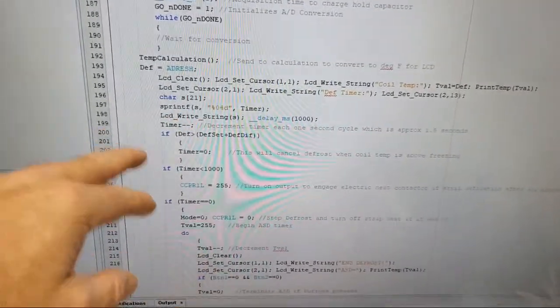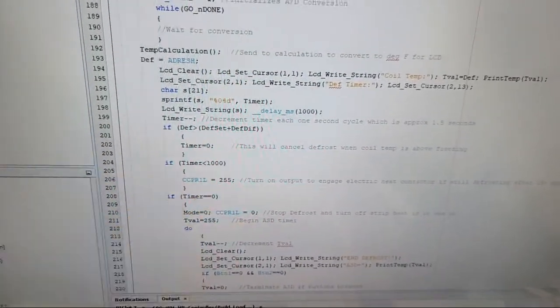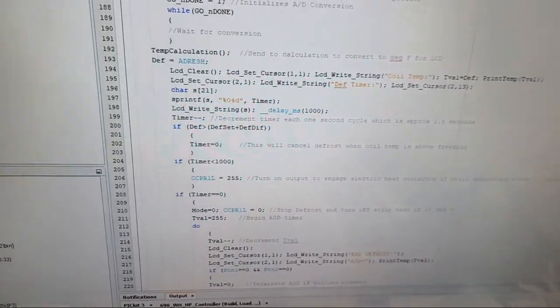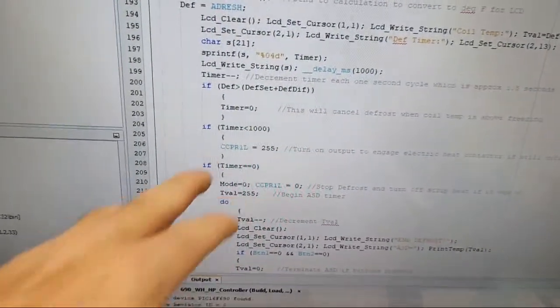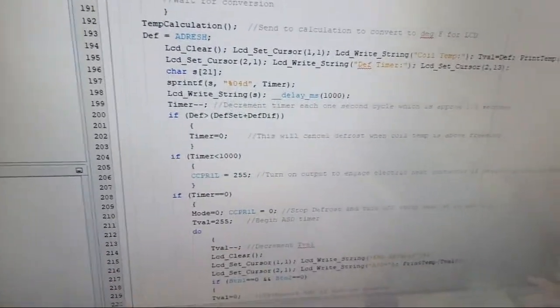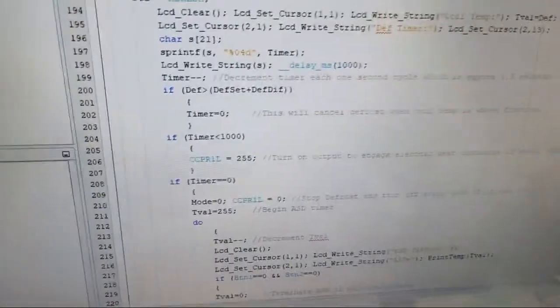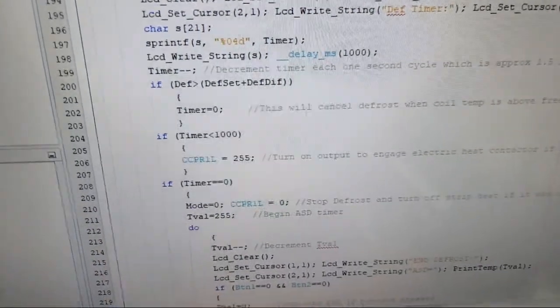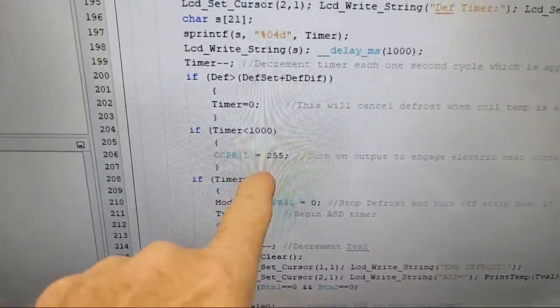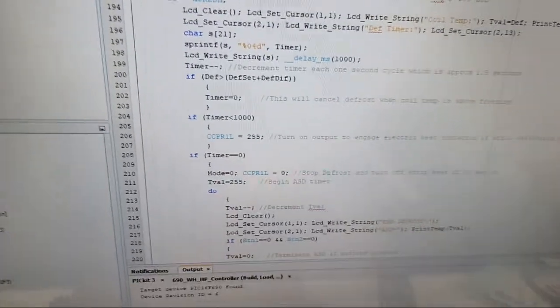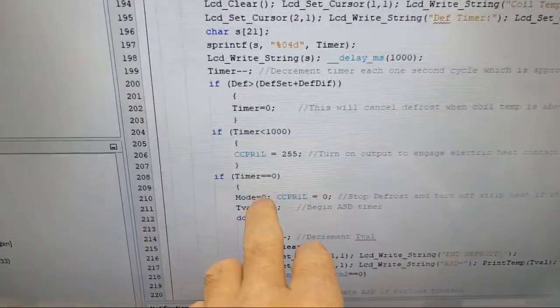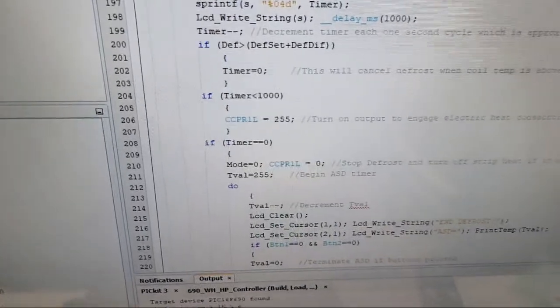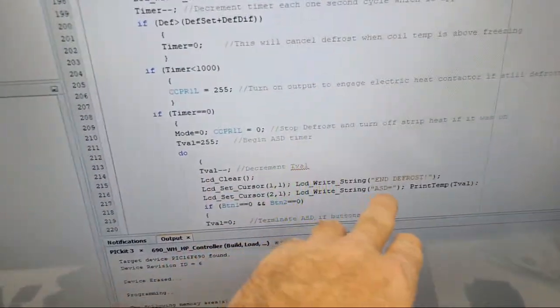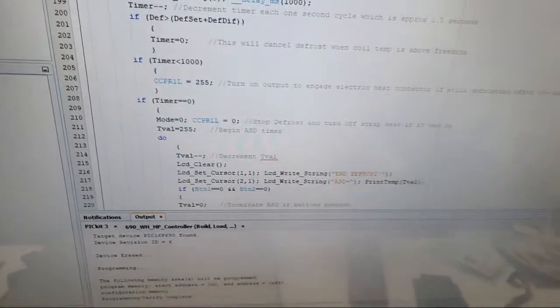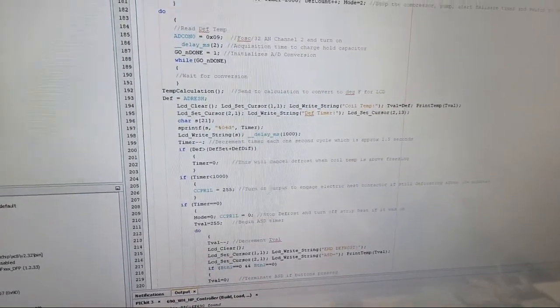So that's what that does after a while, which is right here. I was using the pulse width modulated output, so instead of a binary digital output, I'm just telling it full pulse width. Anyway, that's what that is. And then if timer equals 0, that's when that all elapses, and that's when everything reverts back to mode 0 on that output and all this stuff. And then it's going to just do a countdown for an anti-short cycle delay before it leaves there. That's just in case it's a really short defrost. I always want to give it a good 5-6 minutes before the compressor tries to restart.